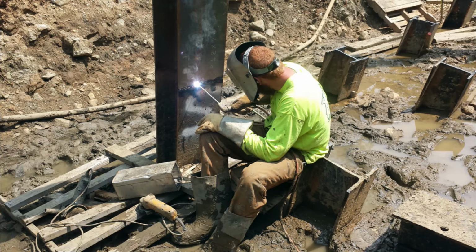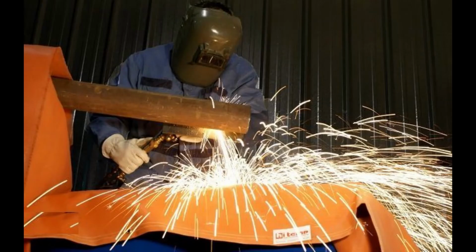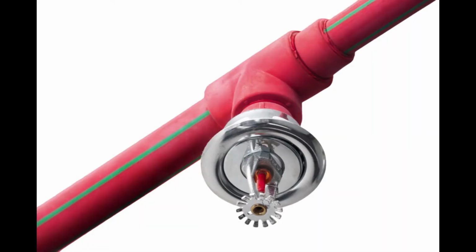So when we talk about a hot work permit, if welding, cutting, or brazing operations can't be conducted in a designated area or a shop designed to facilitate safe hot work operations, then these activities require a hot work permit, as is defined by our hot work program. Now, these precautions help mitigate the risk of fire or explosion. Minimum precautions include that we need to ensure that the building fire sprinkler system is operational at the hot work location. Now, that's if it's applicable. If the sprinkler system, fire detection system has to be disabled, then we need to inform the fire department and the property insurance company. That's something that the GC would do, and define alternate precautions that need to be taken during the outage and then for the duration of the outage.